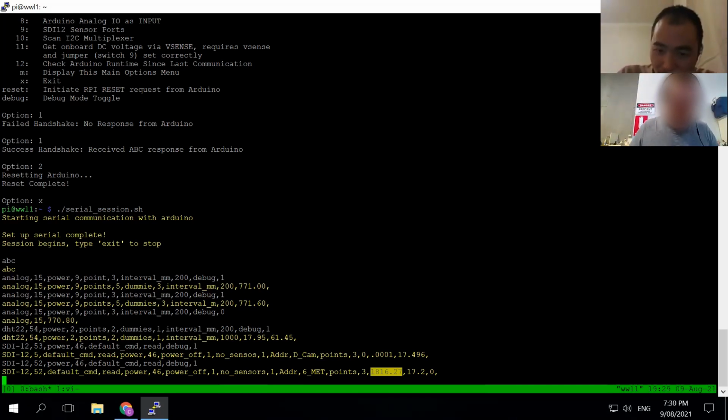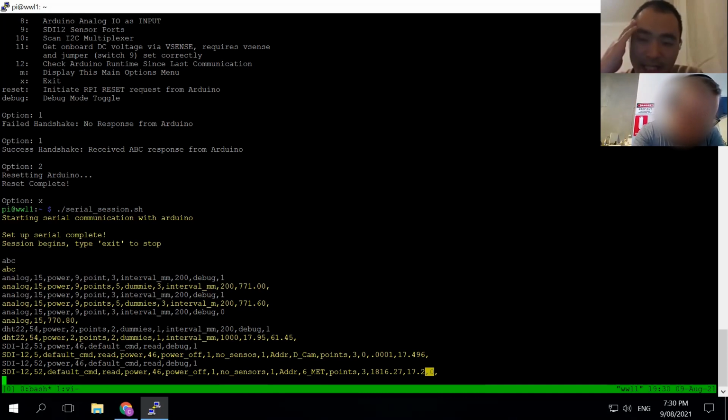So this is definitely the temperature. You see the two values are pretty close. This is EC, electrical conductivity. If it's in the air, that gives you a 0. So that's basically the Meter 3 sensor, which is actually a very, very popular sensor right now, and a lot of people use it. The other thing to bear in mind is that SDI-12 has a longest cable length of 60 meters, so you couldn't go further than that. Perfect.